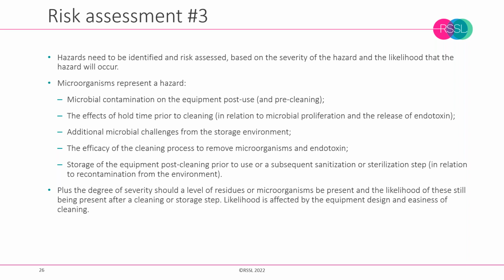Any additional microbial challenges from the storage environment. So that's environment to equipment recontamination. The efficacy of the cleaning process to remove microorganisms and endotoxin. And also then, as I mentioned, the storage of the equipment after it's been cleaned. So all of that also needs to be built into the risk assessment process. And certainly the likelihood of contamination is partly going to be a factor of equipment design and also the easiness of cleaning.